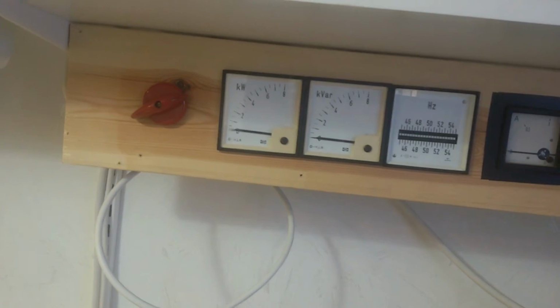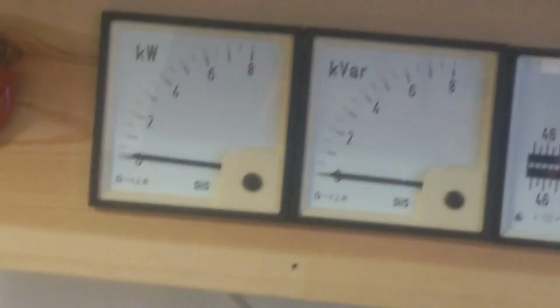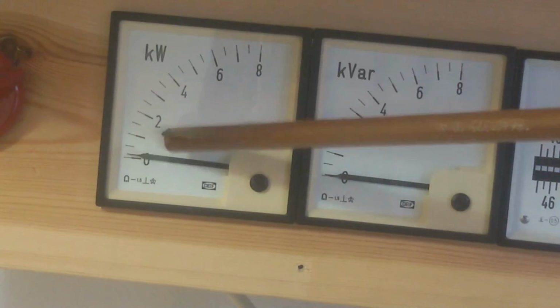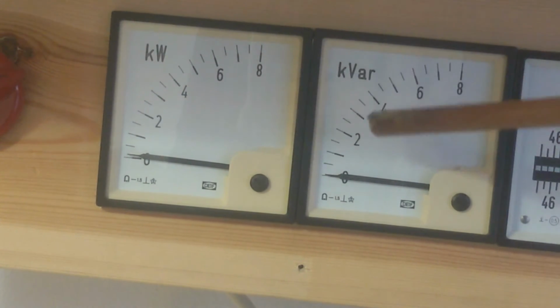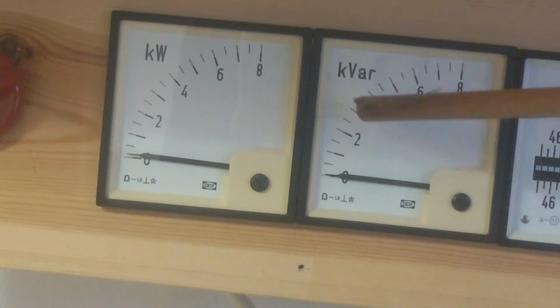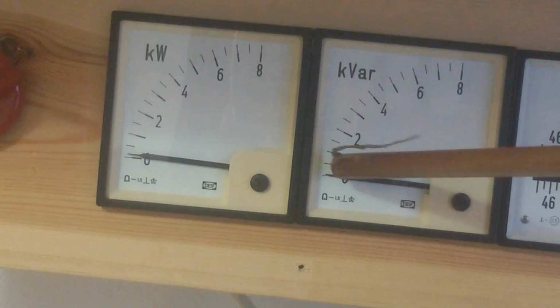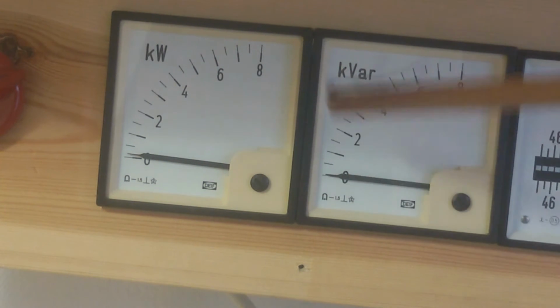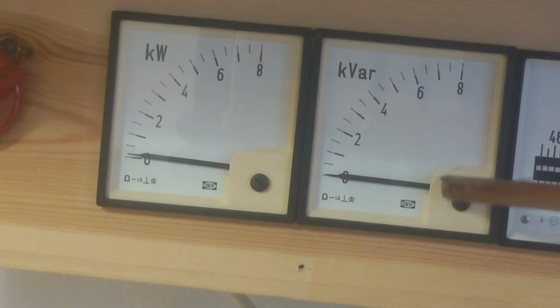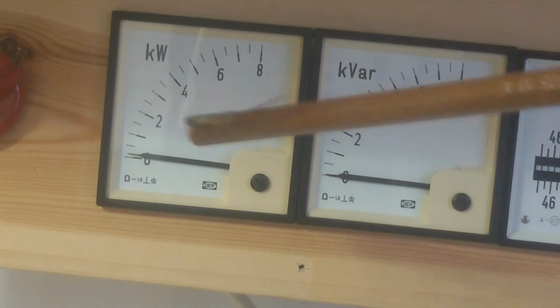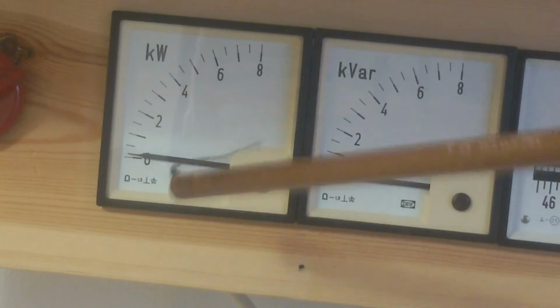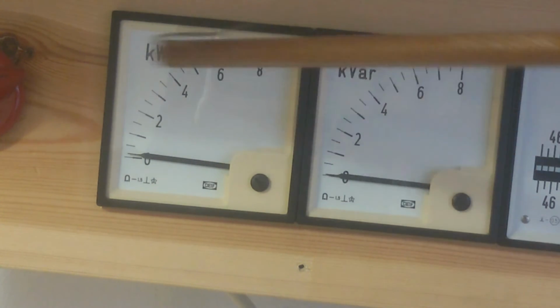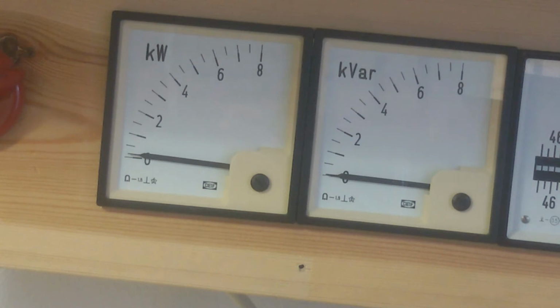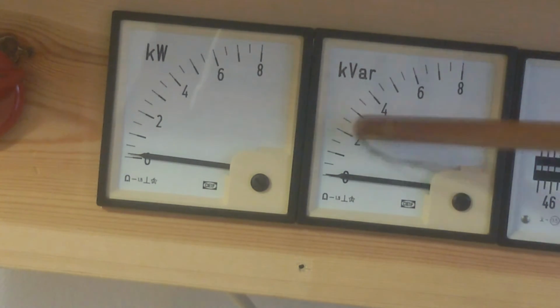That's working, if I have a little bit of load, not much. We want more kilowatts. We don't want kilovolt amp reactive. If I have a lot of kilovolt amp reactive, I need to compensate with some capacitors, because that will just blow fuses with no good reason at all. If I take that one and calculate it with this one, you get the apparent power, and if you have the apparent power, you can calculate it with the active power and get the power factor. When you have the power factor, you can calculate which capacitor you need to use to compensate away this kilovolt amp reactive, or an inductor if it's a capacitive load.